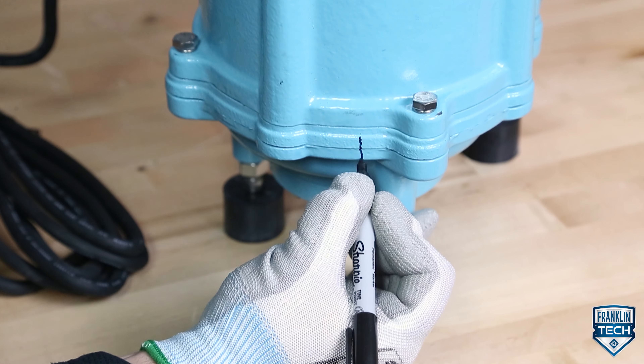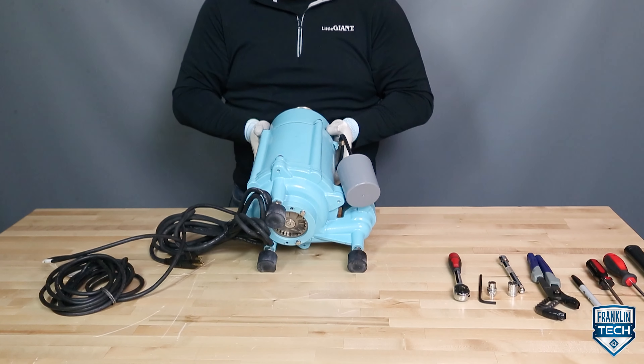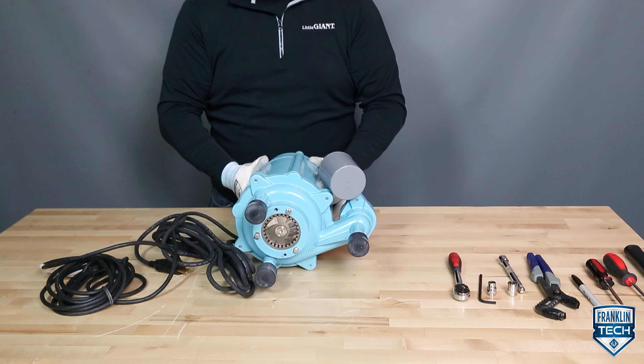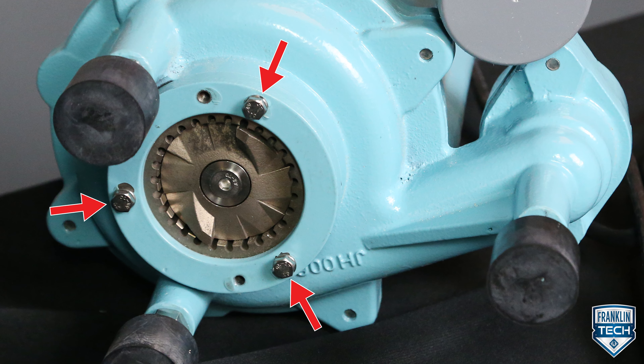Scribe a mark between the seal plate and volute. Next, lay the pump on a smooth, hard surface. Remove the stationary cutter and cutter plate by first removing the three M6 bolts and lock washers with a 10 mm socket or wrench.